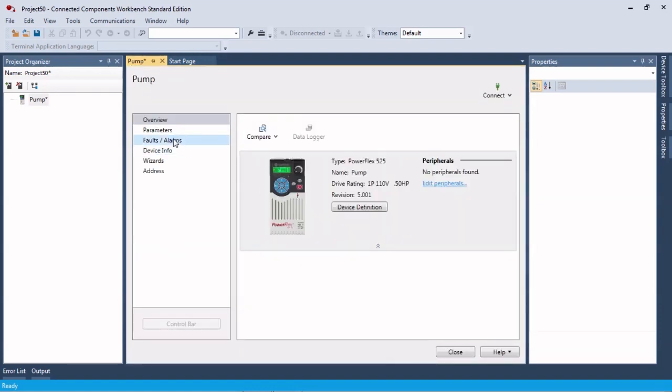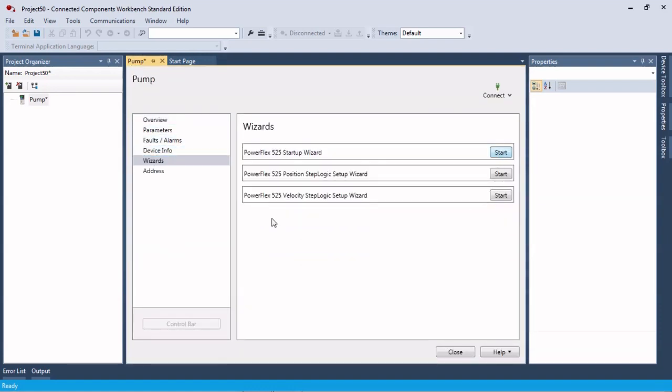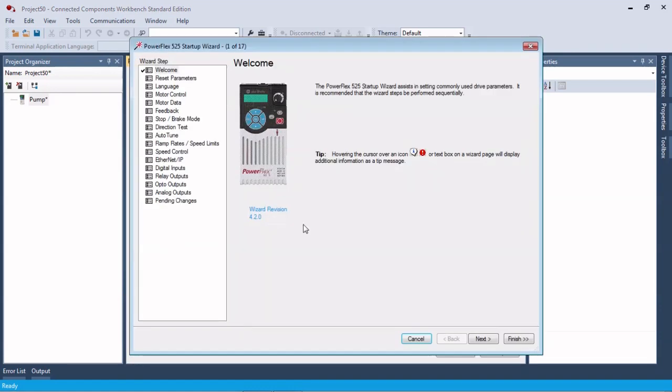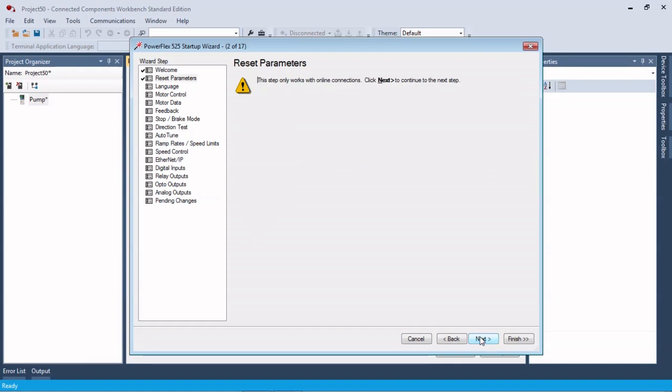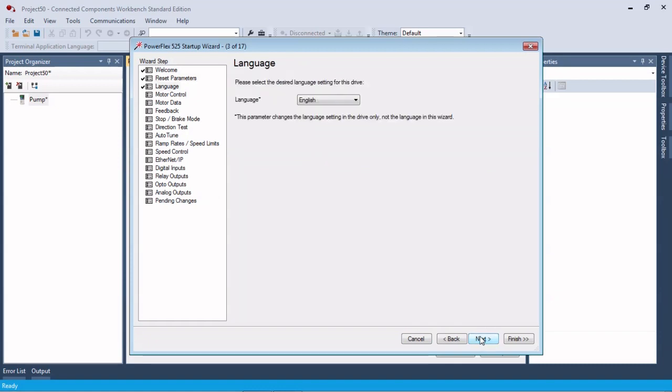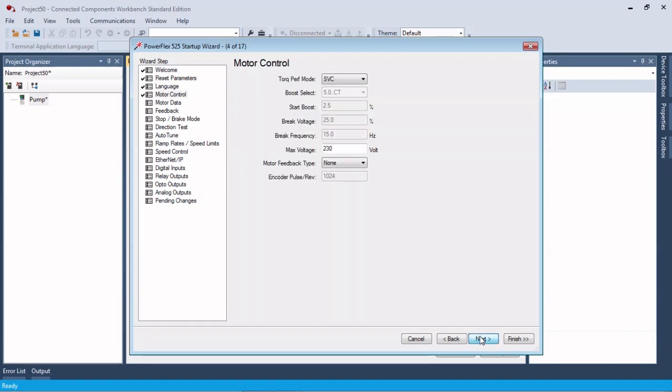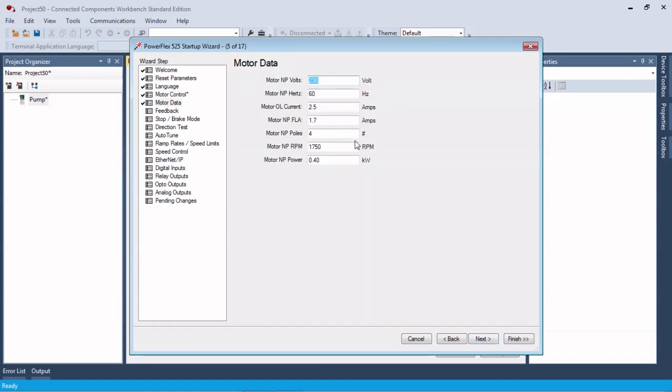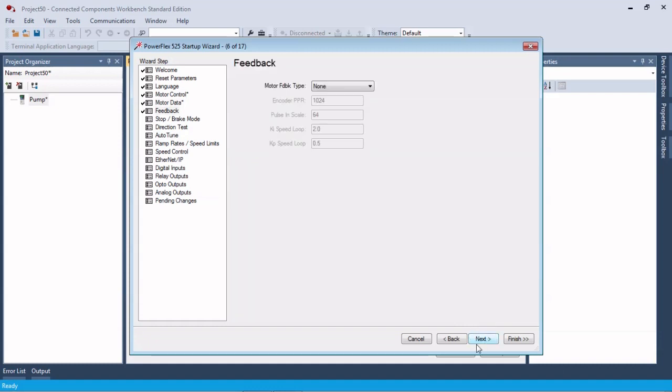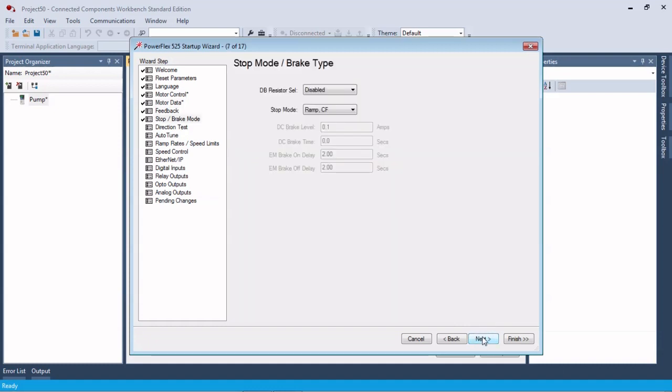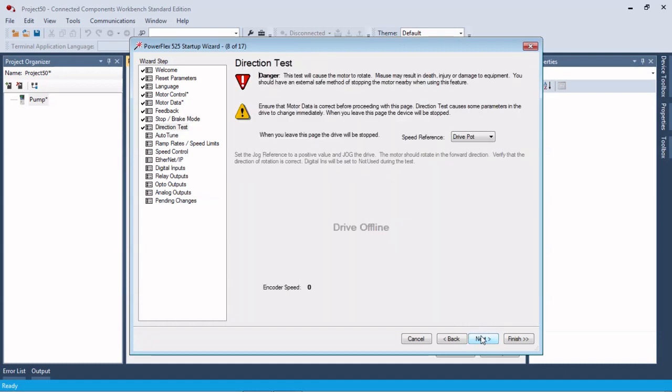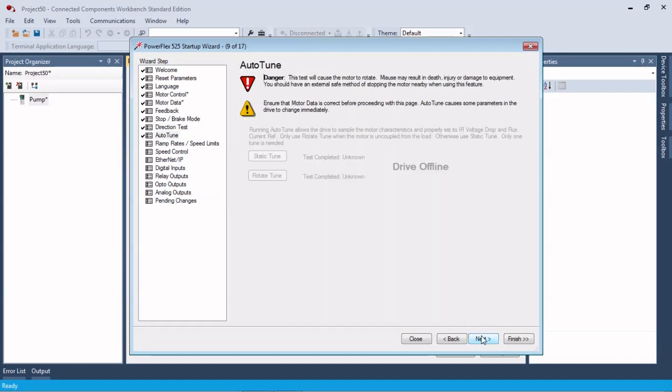I'm going to go through a startup wizard and set the parameters. We're going to set this up for a pump so we're going to go volts per Hertz. If we needed to adjust any of this we could, like taking it to one amp or putting this at 1800 RPM, whatever you need for your nameplate data.